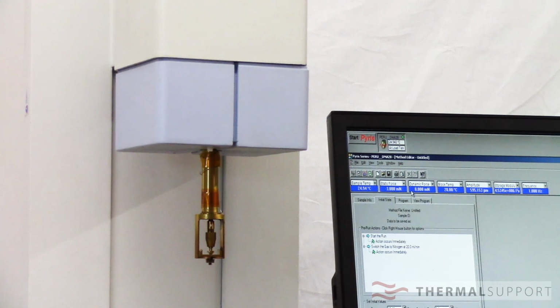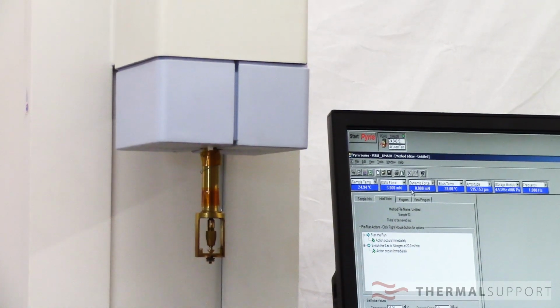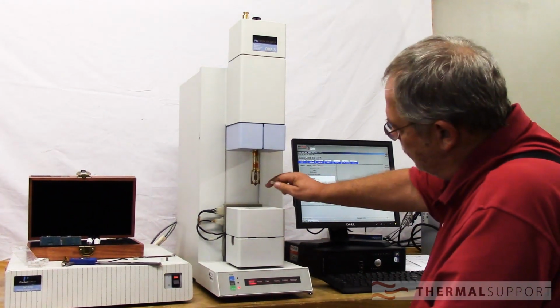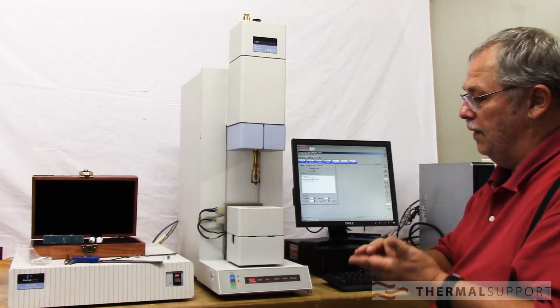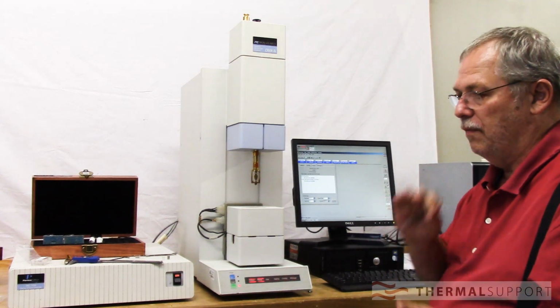The true static force on this thing is -3 millinewtons. Yeah, I think the specs say to set it down to -25, but I could be wrong on that. I like to set it at -3 to -6, mainly for if someone is doing extension or something like that. The thing about this is it's not linear, and so it's really sensitive, and the nonlinearity, we're talking about very small numbers.